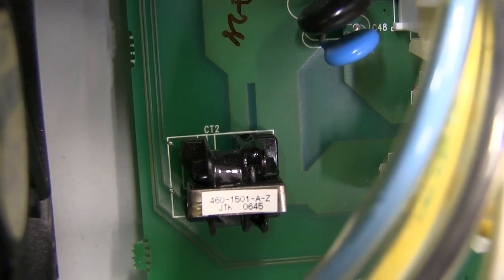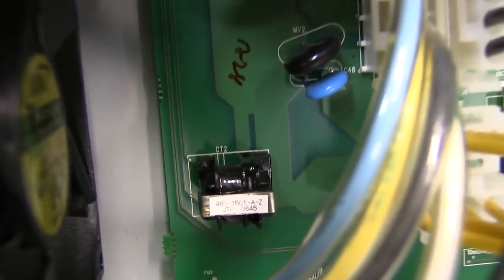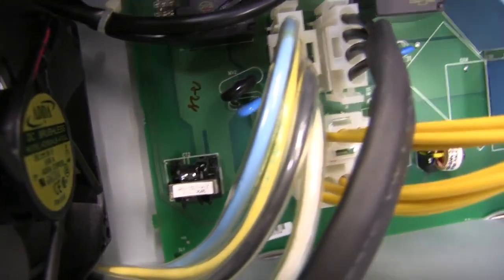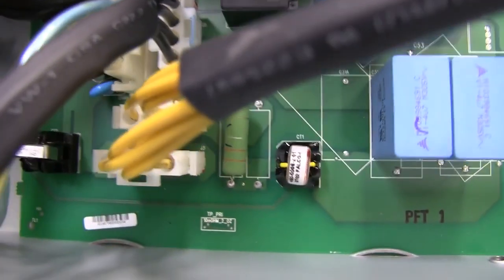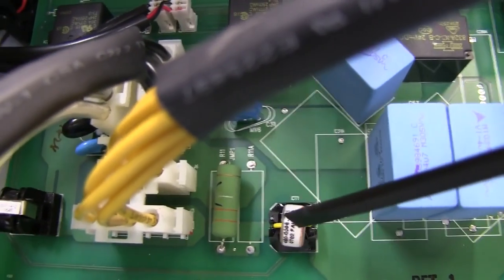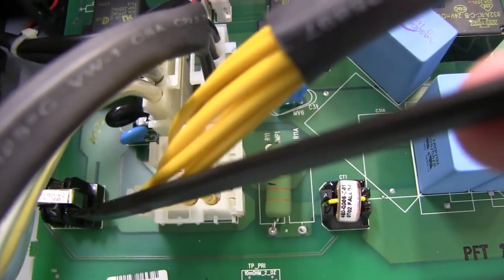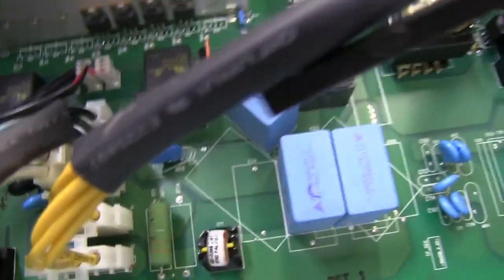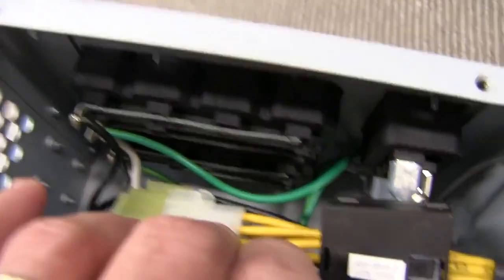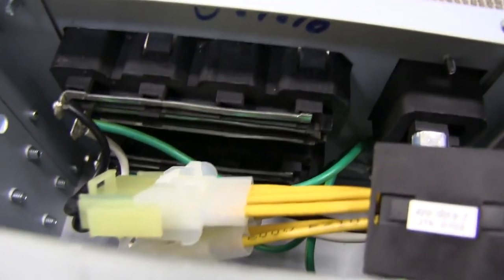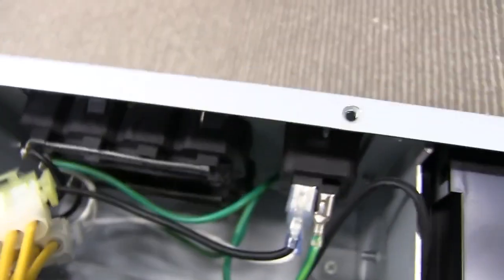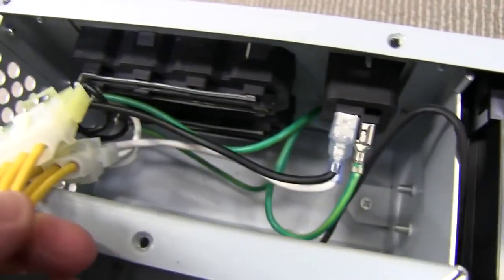And then we've got a bleeder resistor by the looks of it, and another current transformer down in there that would be measuring the output current. They'd be tapping the output voltage as well as the input voltage, reading those so they can get the output power and output voltage. Mains input here, and the other one over here is measuring the output, and these cables bugger off to our output, wired in parallel. They've got a separate wire going off to the 15 amp jack, and all the 10 amp jacks are wired in parallel.